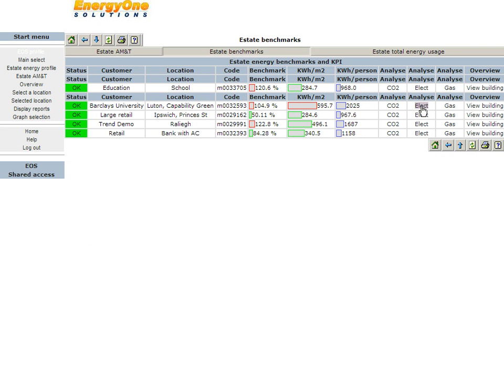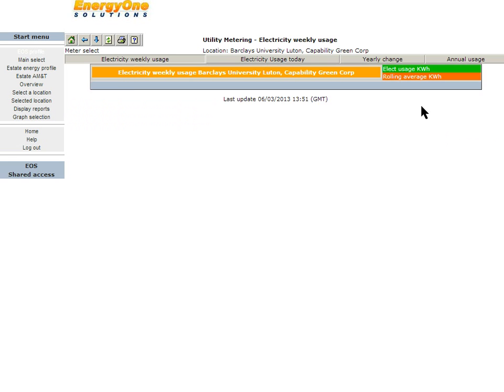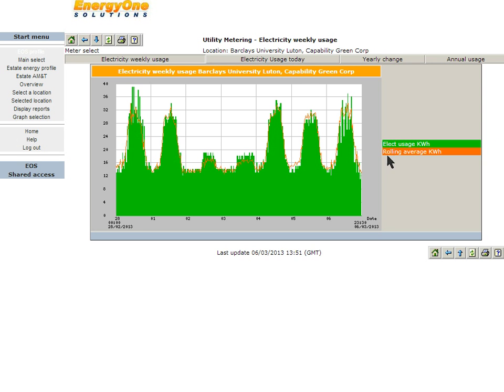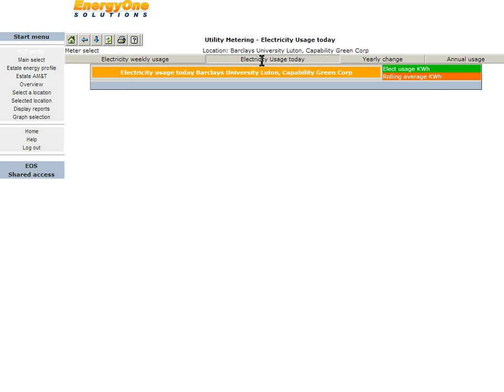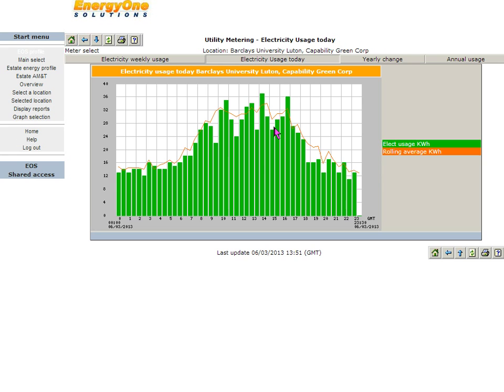In a similar way, this tab shows the same granularity for electricity, along with its annual rolling comparison. By tabbing down to hourly consumption, we can look in almost real time and spot any irregularities that would show up if plant was running outside of the existing rules. This would then suggest that we take a closer look at the analysis graphs for corrective action.